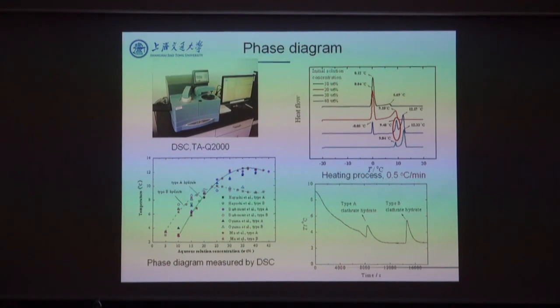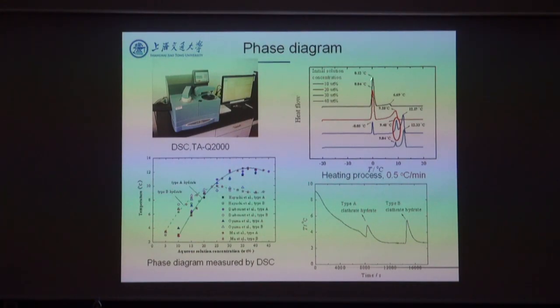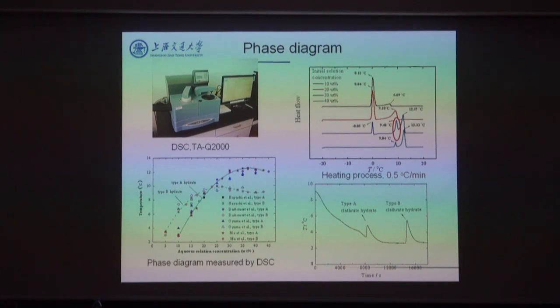Thermal properties are very important. We did many experiments to determine fundamental thermal properties. For the phase diagram, we used differential scanning calorimetry to measure phase change temperature and latent heat. From a lot of experiments we constructed the phase diagram and found that in the TBAB concentration range there are two kinds of hydrate: type A and type B, with some differences between them. For the latent heat, type B typically has about 200 kJ/kg, which is about two-thirds of that of ice, indicating the latent heat is quite high.